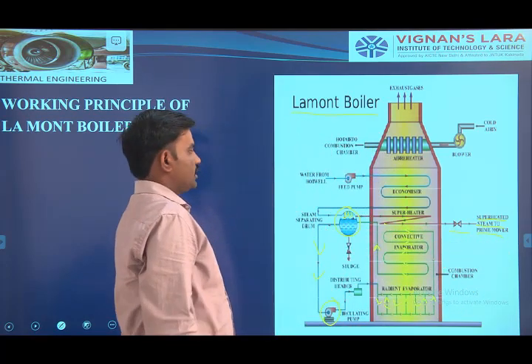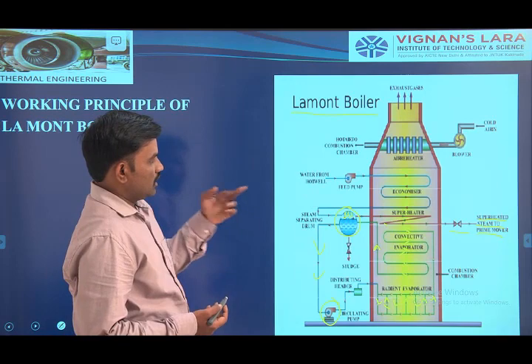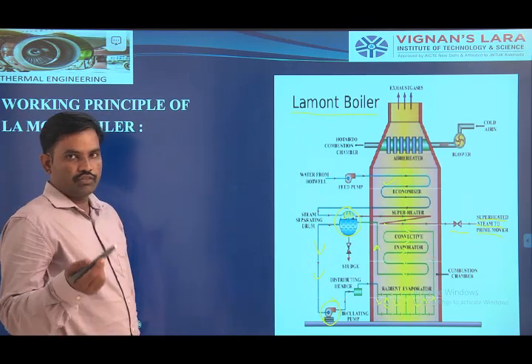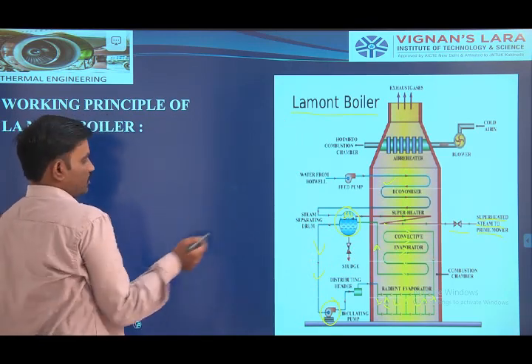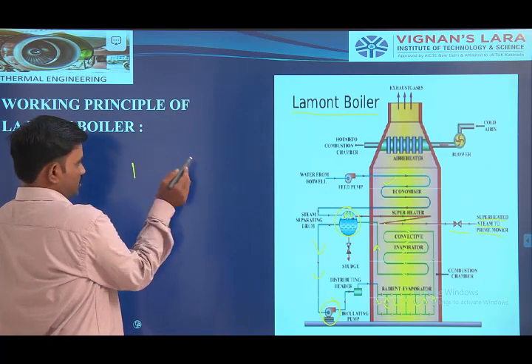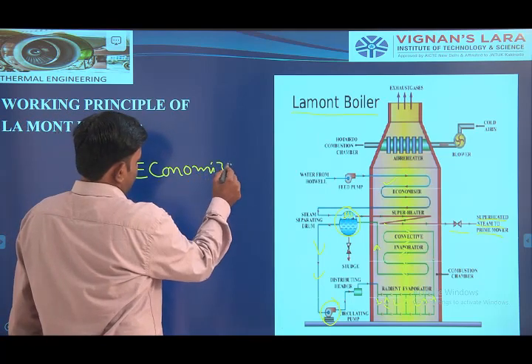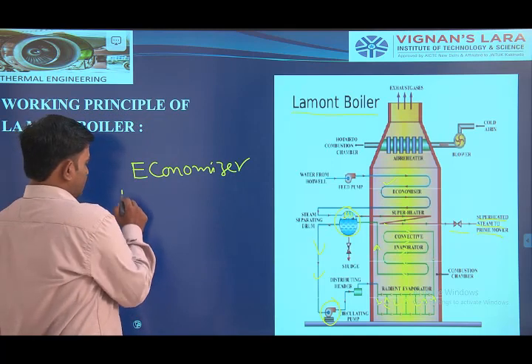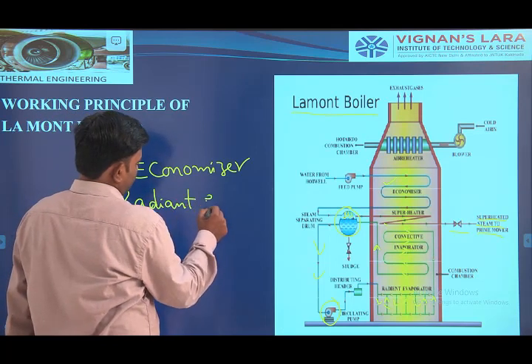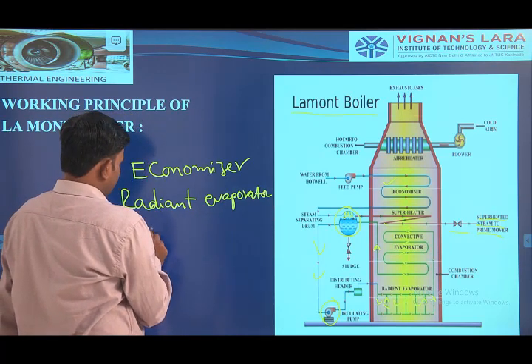Here the prime mover is mentioned — with the help of the prime mover, we are operating the turbine. We are also arranging the economizer here. With the help of these three heat exchangers, we are transferring heat of hot flue gases to the feed water. First we are heating the feed water in the economizer section, later we are heating the feed water in the radiant type of evaporator, and later we are heating in the convective evaporator.